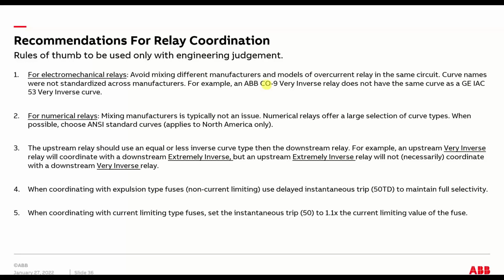For multifunction numerical relays, it doesn't matter, because almost all relays have a whole selection of different curves you can pick. They'll have ANSI standard curves and IEC standard curves. The only thing to remember is whatever you're picking, do the same thing. So if you're going to do ANSI, make sure all the curves you use in various relays are ANSI, and you're good to go. I would choose ANSI standard curves for applications in North America. There's an IEC version of those curves too, which is different. So outside the U.S., Europe, and I think Asia too, would tend towards using IEC type curves.